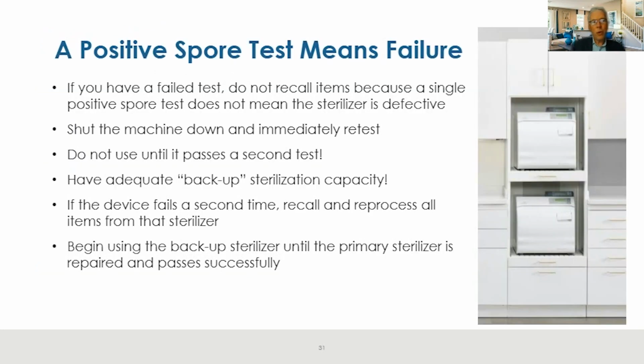So what do you do if you get a positive test, meaning that spore wasn't killed? You open the mail and realize it failed. Don't recall items from that autoclave, because it may be okay. You'll want to retest, but shut that machine down immediately until you get a retest.